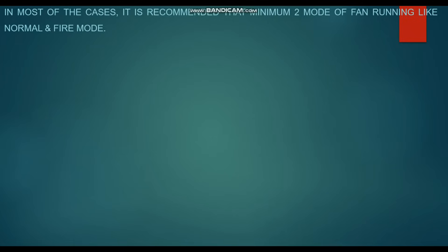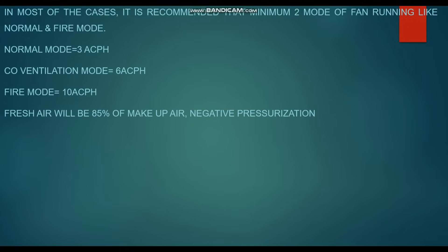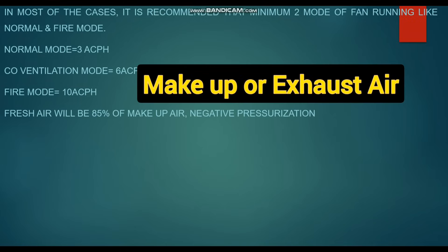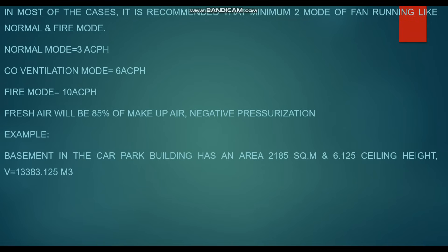In most cases it is recommended to have a minimum of two fan operating modes: normal mode and fire mode. In normal condition the fan runs at normal speed; in fire mode it runs at higher speed. Some civil defense authorities allow three modes: normal mode at 3 air changes per hour (ACH), CO ventilation mode at 6 ACH, and fire mode at 10 ACH. Overall, the fresh air supply is set at 85% of the exhaust to maintain negative pressure in the car park.